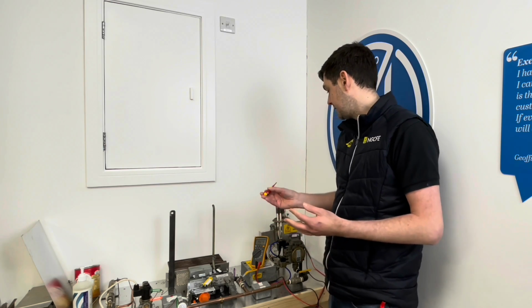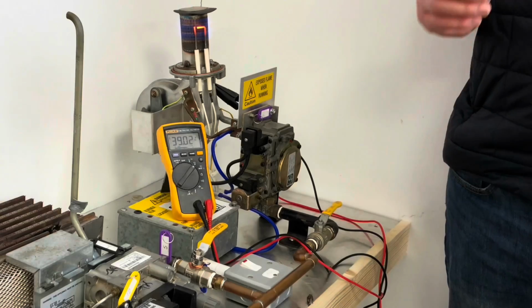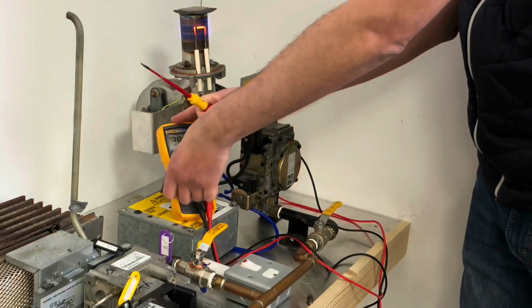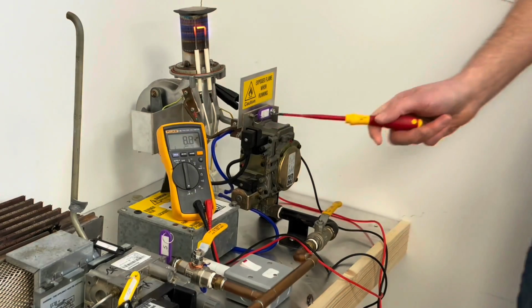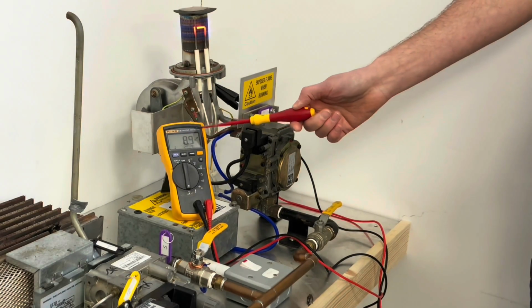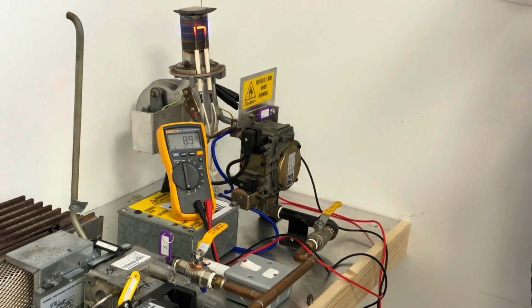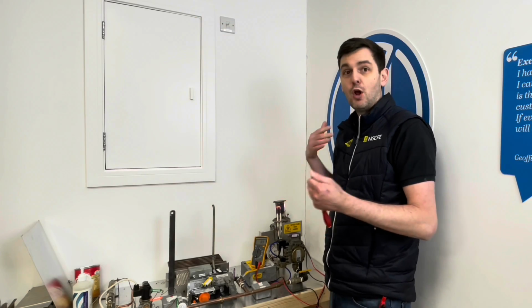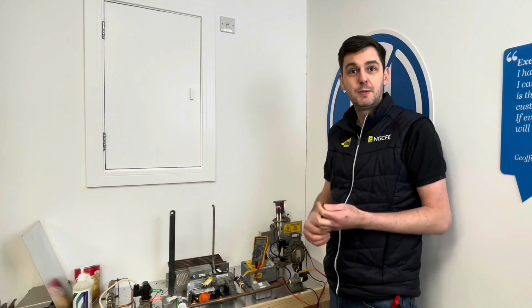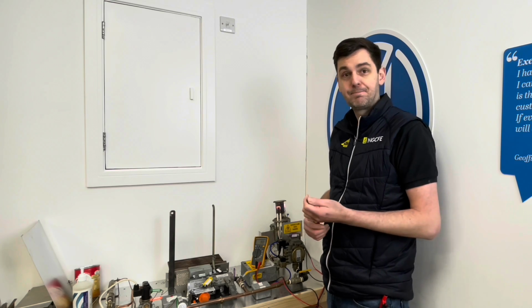The other way we can test is with microamps. So if I change that to microamps, we're getting a reading of 8.8 microamps. Again, that's DC current. And what that is, again, an indication of is the strength of the flame, how well the flow of ions through the flame is being conducted back through the circuit.